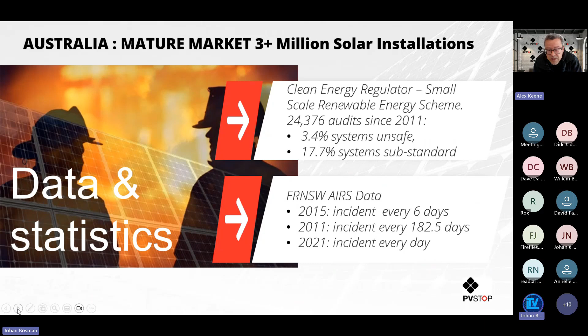Just to confirm, the DC danger zone is the wiring from the solar panel to the inverter, where DC electricity is converted to AC so it can be used in the structure or elsewhere. So there's potential for fire, electric shock, and, depending on where the PV system is located, falls from height. There is no safe, reliable means of isolation. When we say isolation, we really mean complete de-energizing—a solution that eliminates the hazard by taking away the electrical supply completely. Isolation generally means containment or separation of the electrical current in a safe way, holding the electricity safely so human lives aren't compromised.